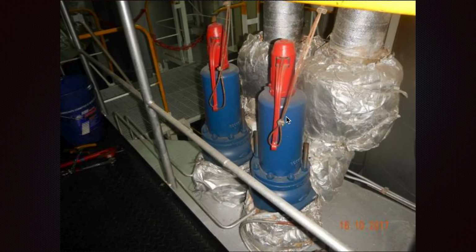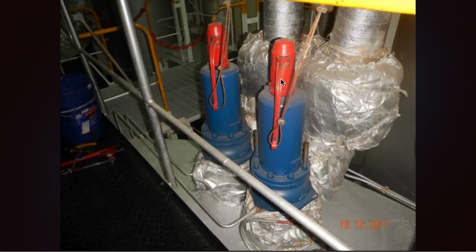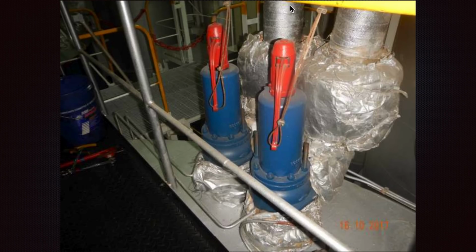In this case, we got some damage to the bracket here, which was bent because the positioning was not proper. So we already created one problem which made a replacement necessary. We cannot say luckily, because somebody ordered that spare, we had it and we replaced it. But anyway, we identified that problem and resolved it by positioning the wire cable exactly in the middle, so it will function up and down.